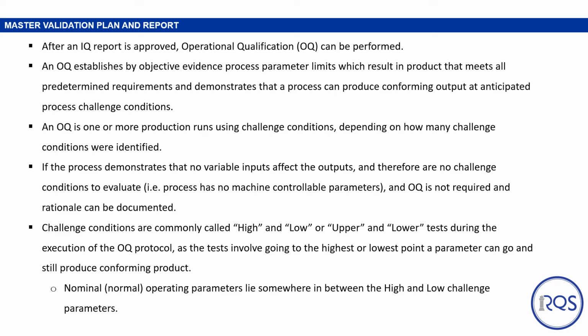If the process demonstrates that there is no variability in the inputs that would affect outputs, and therefore there are no challenge conditions to evaluate, an OQ is not required and a rationale can be documented. And as mentioned earlier, challenge conditions are commonly called high and low or upper and lower tests during the execution of an OQ protocol, as the tests involve going to the highest or lowest point a parameter can go and still produce conforming product. Nominal or normal operating parameters lie somewhere in between the high and low challenge conditions. Once we have the OQ and all of the high and low conditions, the high, the low and the normal all together represent the process window, and the equipment can operate at any point in that window.